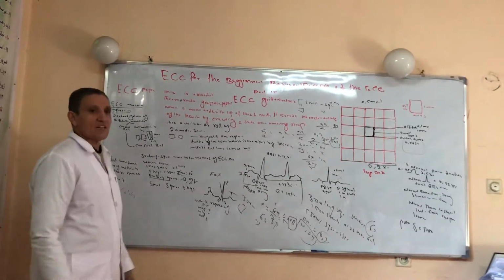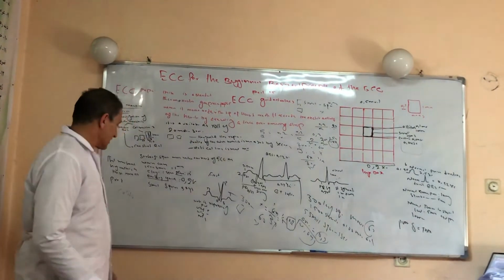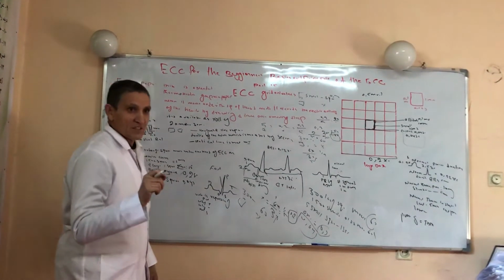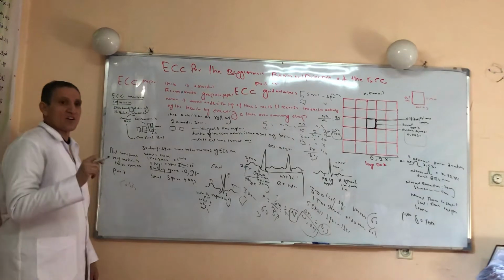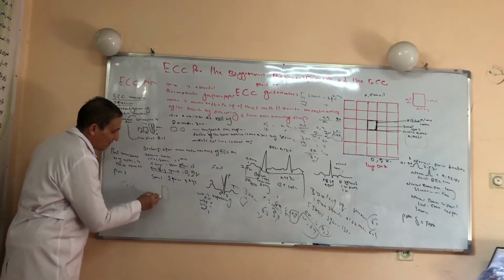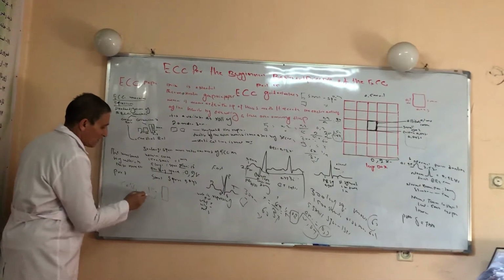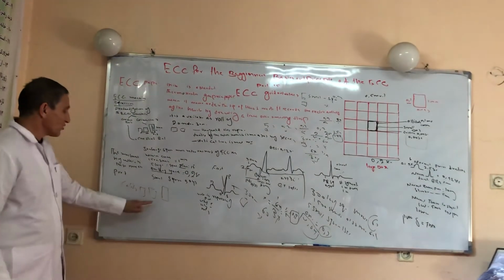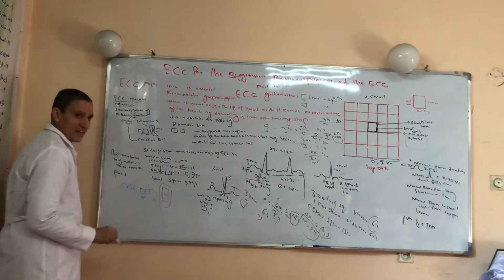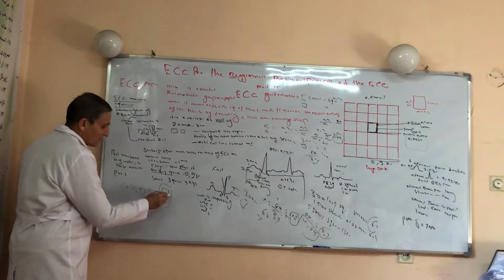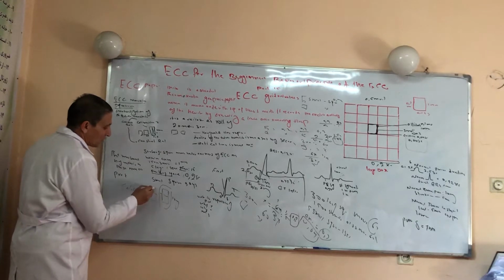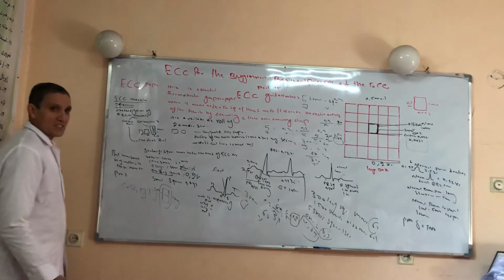What is the calibration signal? It is a signal of 1 millivolt which displaces the needle of the ECG machine up to 2 large squares. Which one is correct? This is the 2 large squares, 10 millimeter amplitude, which represents 1 millivolt.